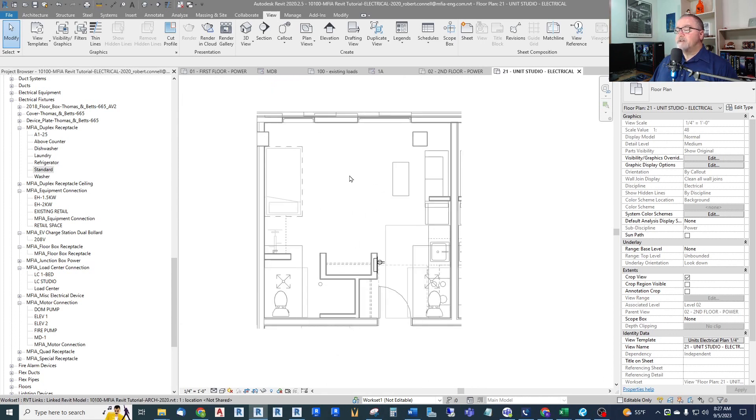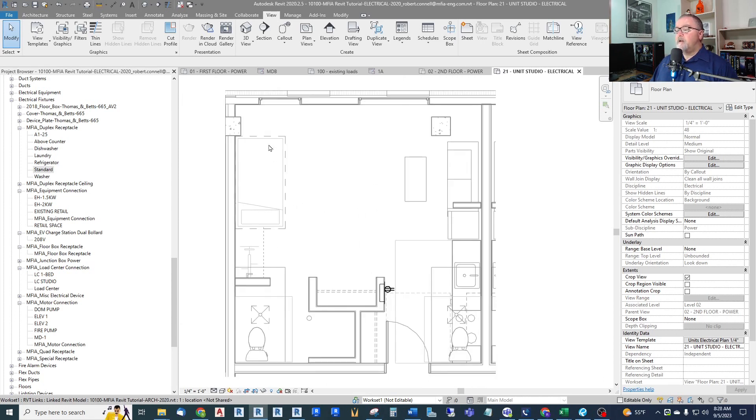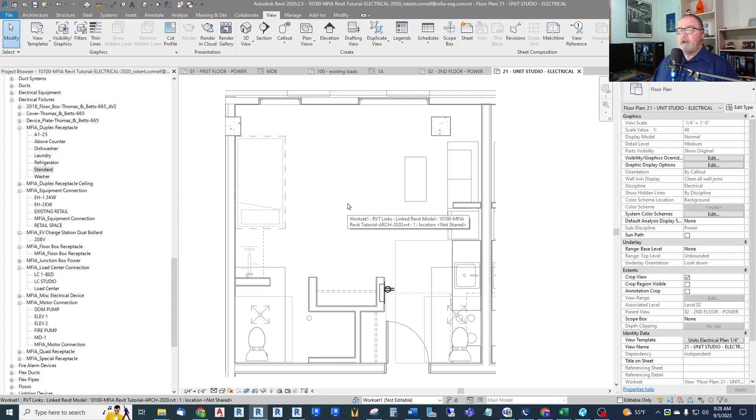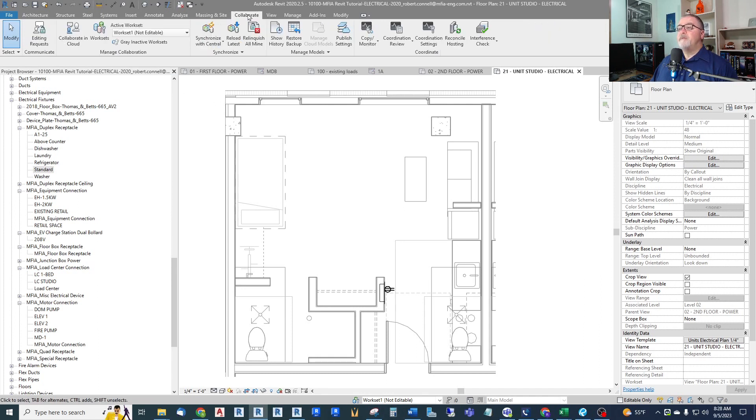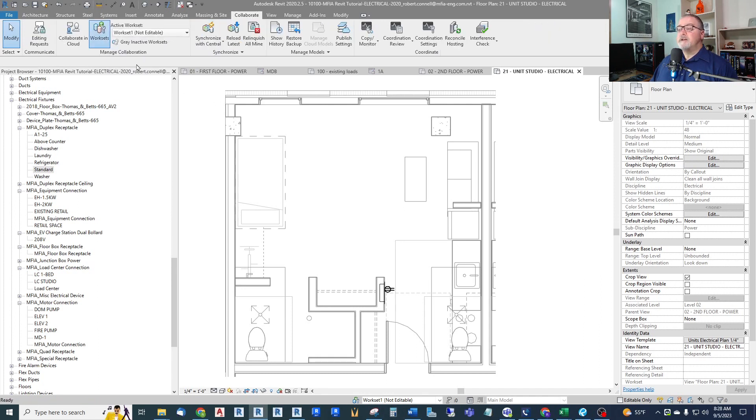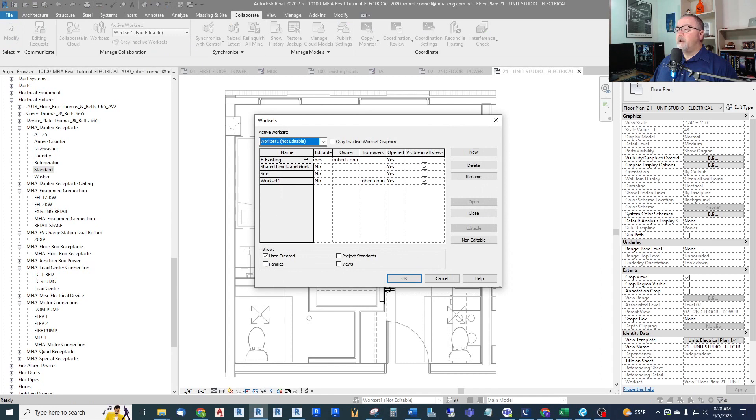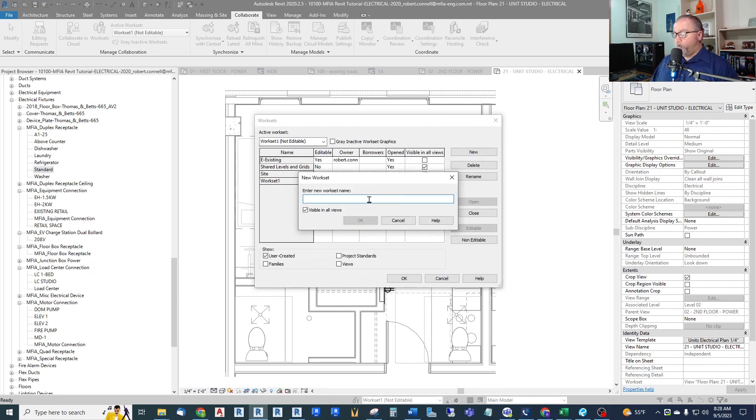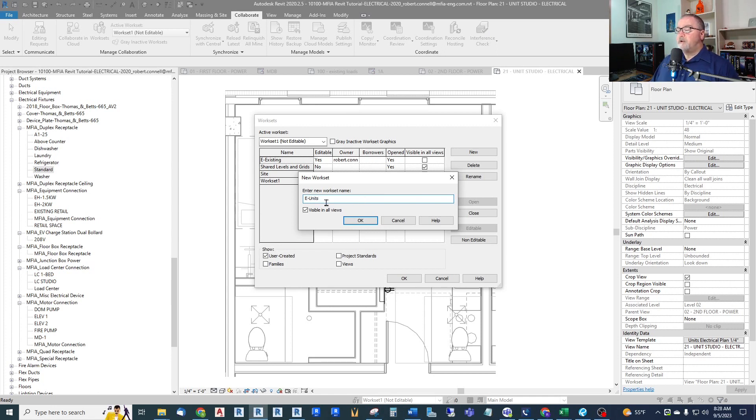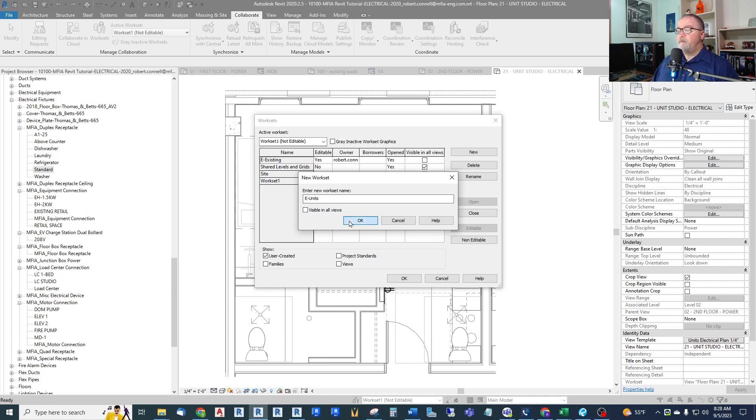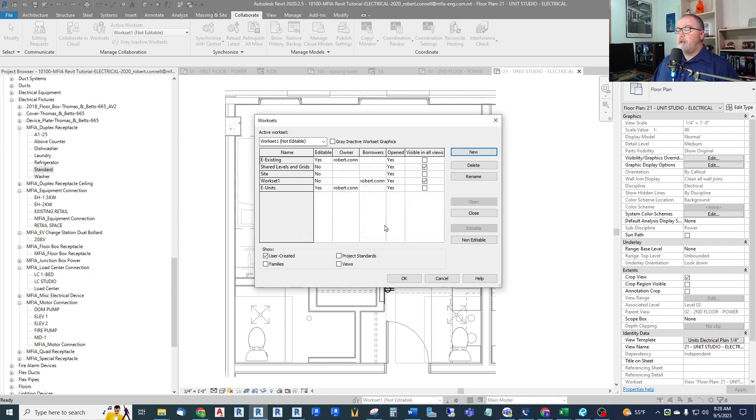Well, the way I deal with that is to create a separate workset just for equipment and receptacles. What I do is I just create a separate workset for items that are inside this apartment, any apartment unit. So I will go up to my Collaborate tab, Worksets, and let's create a new workset. And we're going to call it, I always put an E in front of it, E-Units. Visible in all views? No, it's only going to be visible in my enlarged unit view. So the default will be not visible. And then we will have to enable it.